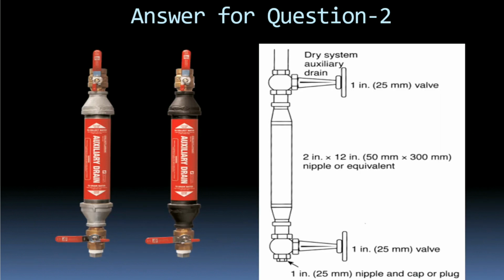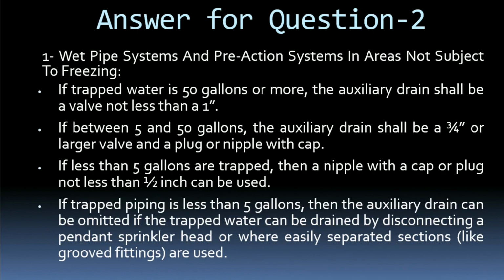That means you see this type of arrangement here, like we have a 2 inch by 12 inch nipple. This is for another system, but I am just telling it as an example. So we will propose this type of arrangement with different valve sizes. The first: 50 gallons or higher, then we go with 1 inch. 5 to 50 gallons, then we go for 3/4 inch, and less than 5 gallons, then we can go with half inch. But if it is less than a gallon, then we can avoid the auxiliary drain also.